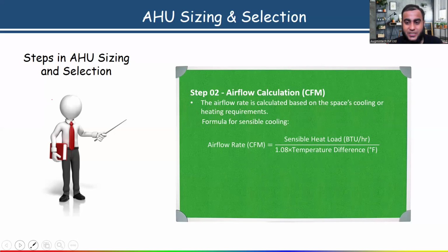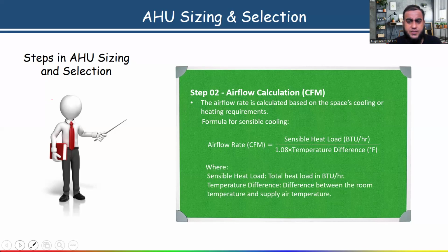For that, we have a formula to calculate the airflow rate in cubic feet per minute. The formula is: sensible heat load in BTU per hour divided by 1.08 times the temperature difference. Here, sensible heat is the total heat in BTU per hour. Temperature difference means the difference between the room temperature and the supply air temperature. And 1.08 is the factor we are using here. Now, maybe many of you have a question in your mind: sir, while calculating the airflow CFM, you have considered only the sensible heat load. Why have you not added the latent heat load? Remember, while calculating the airflow rate, we only have to consider the sensible heat load, because sensible heat load directly impacts the airflow.